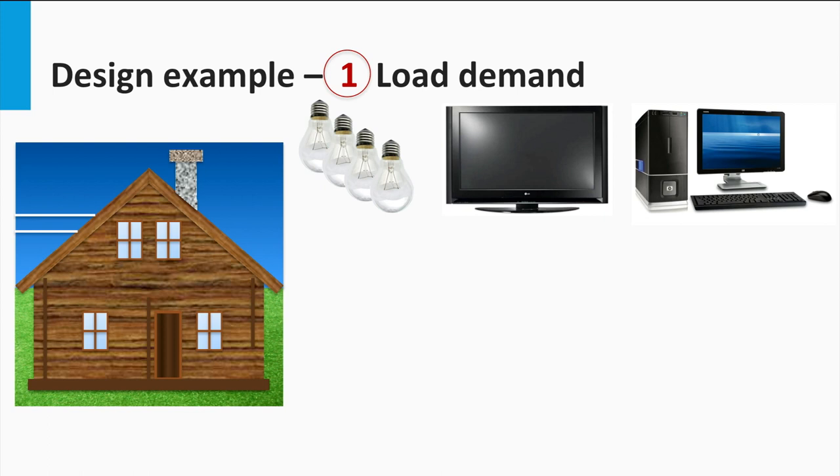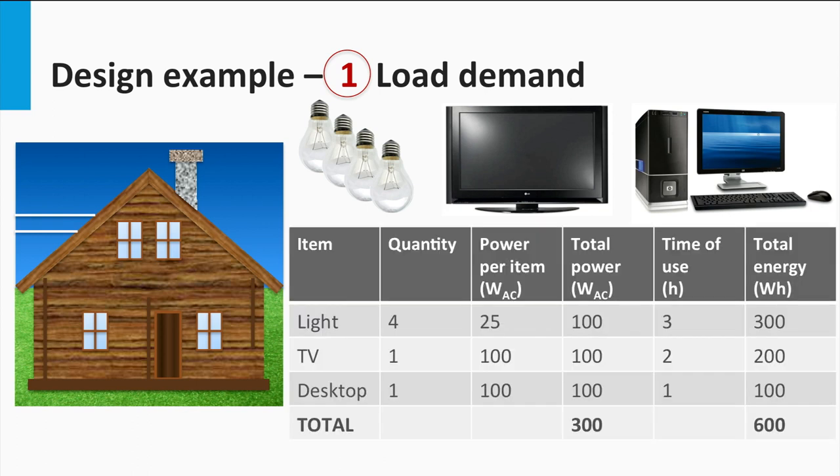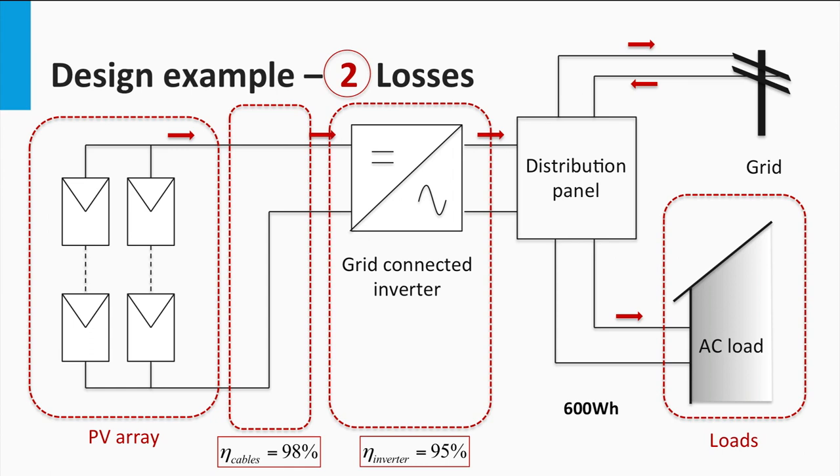Let us consider a similar load demand as shown in the stand-alone PV system design example of the previous block. The required quantities of each kind of load, along with the duration of usage, are mentioned. Note that all the loads in this system are AC loads. The total power and energy requirements have been tabulated here as well. Another main difference here is that there is no concept of autonomous days, as there is no storage. Instead, the electric grid acts as a limitless storage. Let us first account for the losses in the system. This would help us find the energy needed at the output of the PV array to successfully cover the daily load.